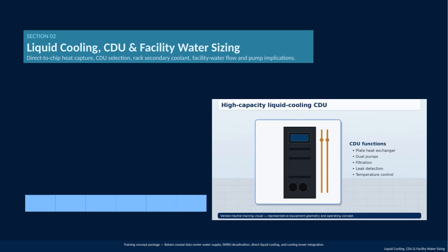Now we're diving into Section 2, which focuses on liquid cooling, CDU selection, and facility water sizing. Here, we'll explore how direct-to-chip heat capture works and why choosing the right cooling distribution unit, or CDU, is critical for efficient thermal management. We'll also cover the role of rack secondary coolant systems and how they influence facility water flow and pump requirements. This training module uses a Batam Coastal Data Center as a case study, integrating real-world elements like seawater reverse osmosis desalination, direct liquid cooling technologies, and cooling tower systems. Understanding these components and their interactions will give you a comprehensive view of how to design and size cooling infrastructure effectively for high-performance data centers.